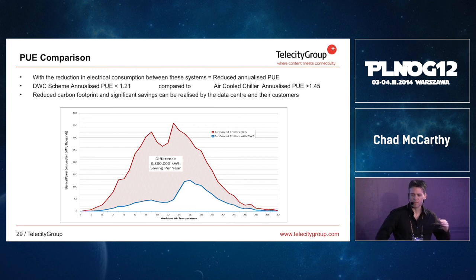Before we move on from this, I would just point out the slightly unusual shape of the diagram. The temperature data of any particular location is normally a kind of bell curve. And the reason why you've got this big chunk bitten out of the top of the red curve is because with a modern compressor, Turbocor type chiller, first of all, the system runs as long as it can on the free cooling, and then when the chiller actually finally does start, we actually have a decrease in electrical energy. And that's because the chiller is more efficient than the fans running at full speed at roof level. So after the chiller starts, the cooling water temperature increases significantly up to 45 degrees, which compared to atmosphere is significantly warmer. There's a bigger delta in the temperature, which means the fans at roof level drop in their speed, and that's why you have this. That can be flattened out with better tuning, but it's a typical characteristic for the standard setup.